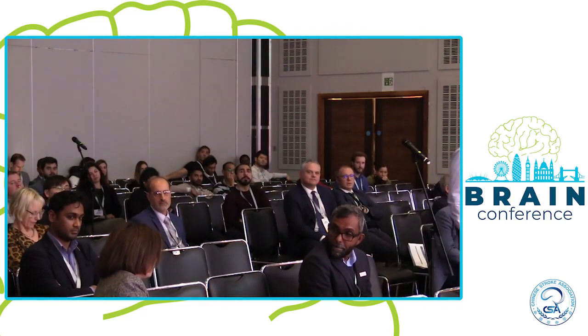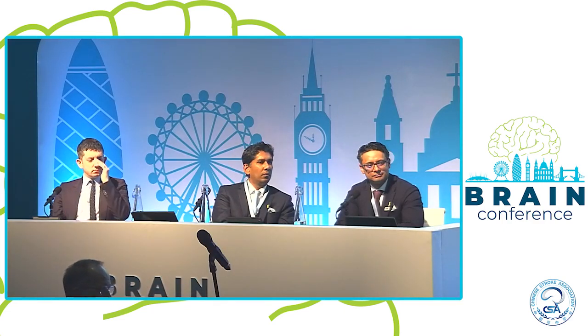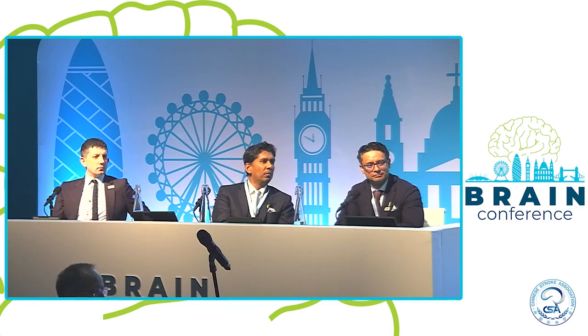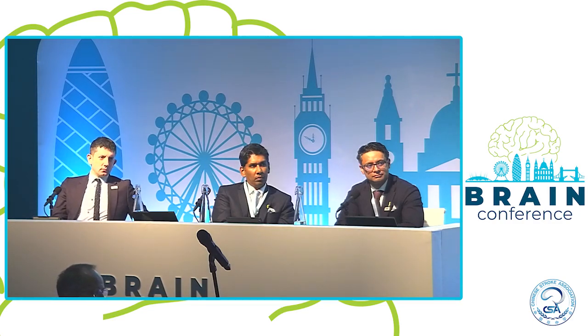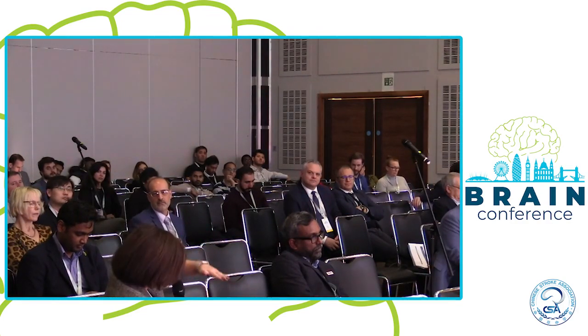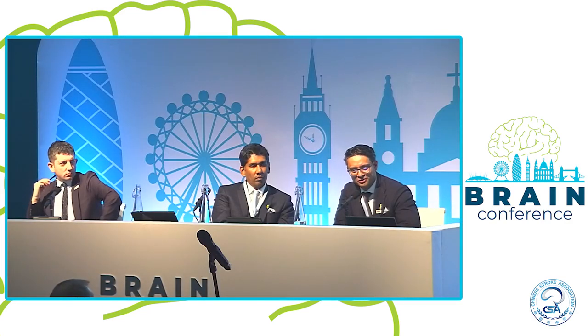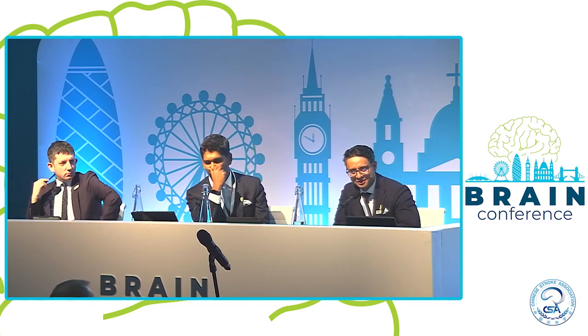We have actually taken your feedback. I don't have my slides here with me, but I'll show you at the break. The new models that we launched, especially the 5.5, actually have proportionally less radial force than even our smaller models. We always take your feedback into account. We've made the radial force much flatter and a little bit less in our newer models. Having worked with you, Tommy, the answer generally from me is, yes, I agree.